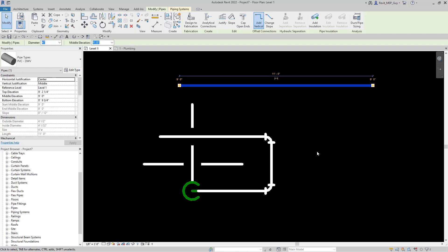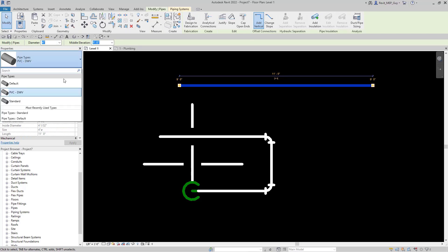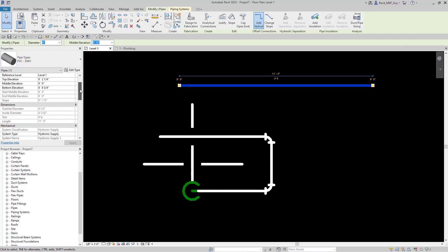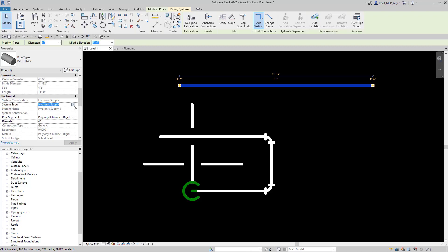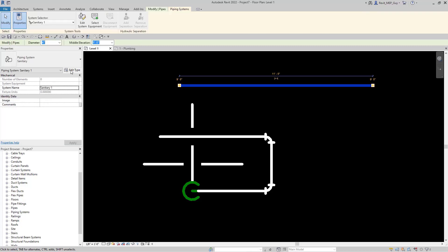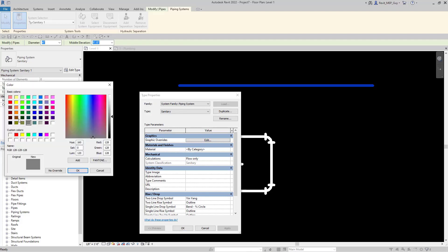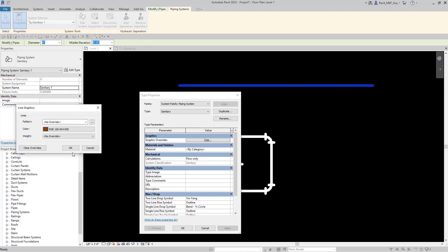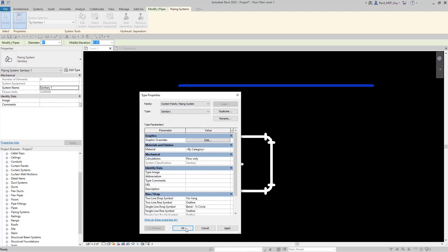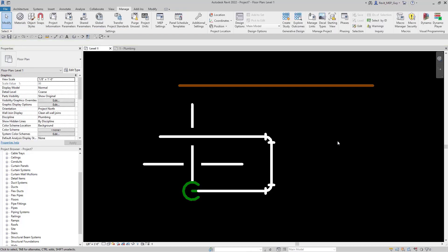The next display property I want to set up correctly is my system display. Since we're on a PVC type pipe, I'm going to make sure the system is sanitary piping. Now I'm going to go to my piping systems, click on edit type, and we're going to edit these graphic overrides for our sanitary piping to show up as a brown line. Hit ok. And now you can see my sanitary pipe is displaying in a brown color.